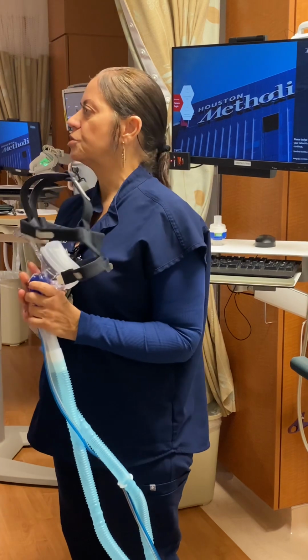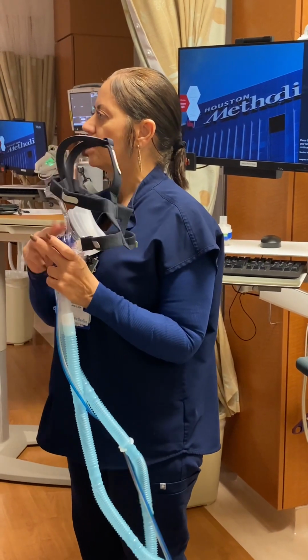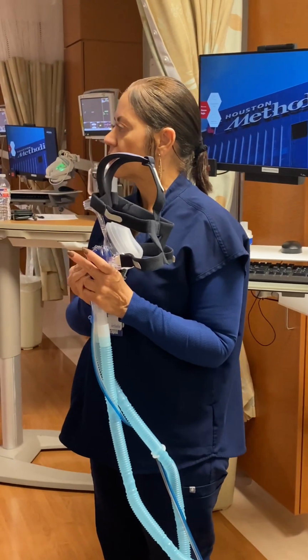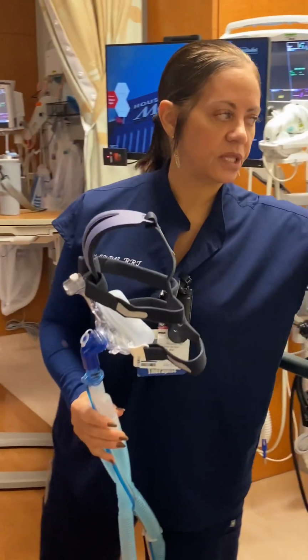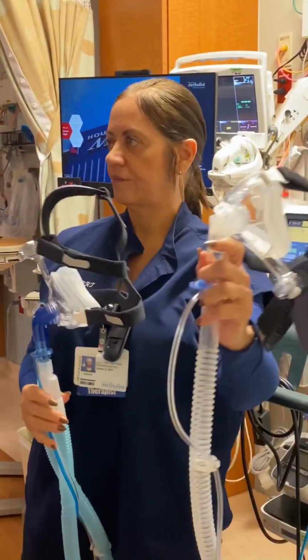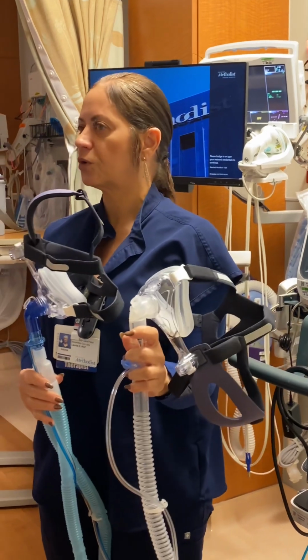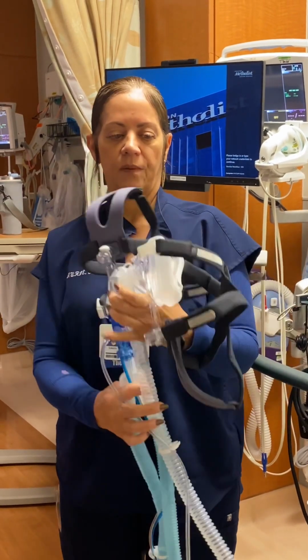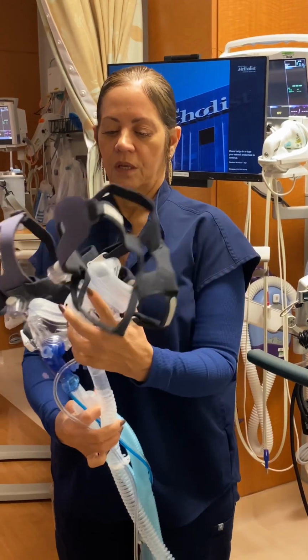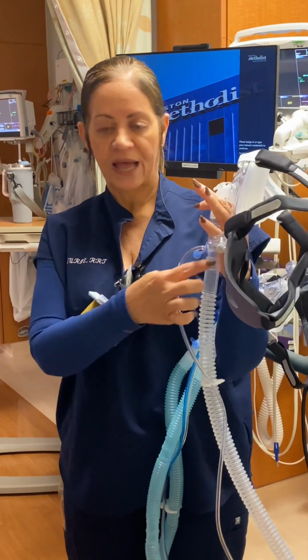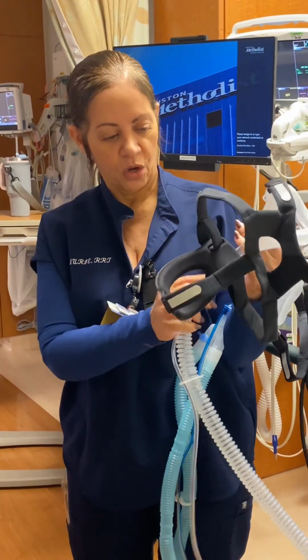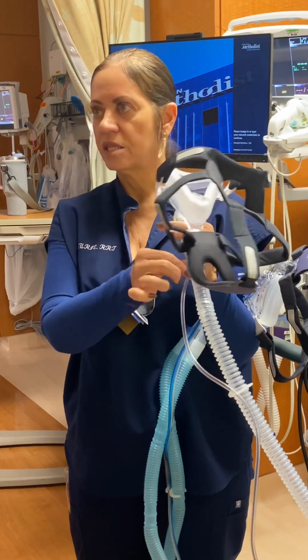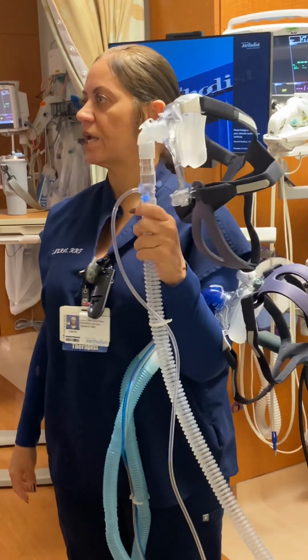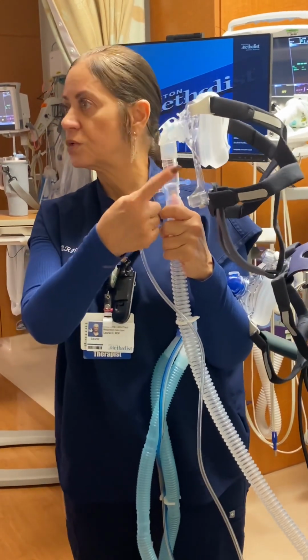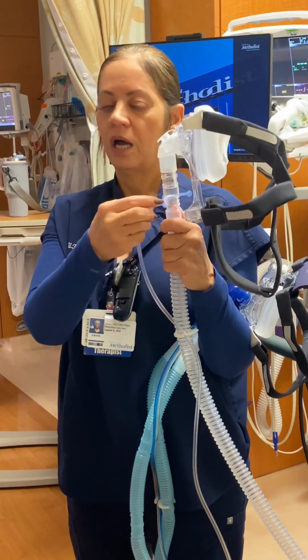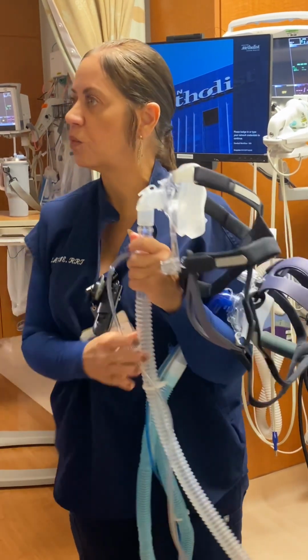This machine is set up a little different. Respiratory knows there's a different adapter, another elbow that goes on this one. It's a little different as compared to this one that comes out the pack like that. But that's something respiratory can work on, okay, for you. There's an exhalation that should never be closed up on this side. See this little thing here? Never close it up. They will retain CO2 like that because it closes up the exhalation port. Normally, I tear it off, so no one makes that mistake.